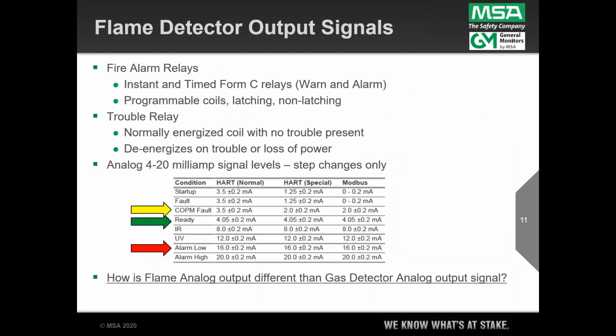So starting from the top, probably the most common signal outputs we see used in the field are fire alarm relays, and our devices and many in the market provide two. One is called instantaneous, or the warning relay, but its function is instantaneous. The minute it senses energy in excess of the alarm threshold setting, it energizes that instant relay, and so those contacts close. Then there's a second relay called timed or alarm, but I like the word timed. Another term would be sustained.